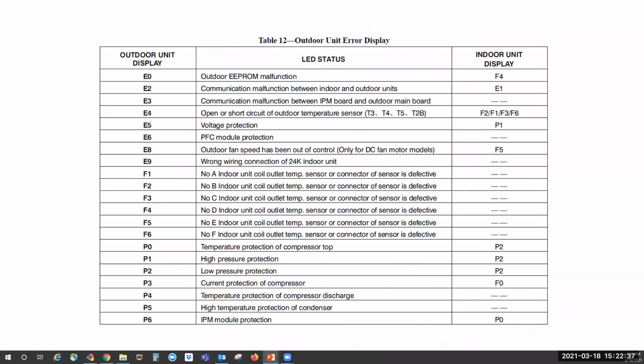If you have an error code indoors, you want to go outdoors and make sure that error code matches. You'll refer to your service manual for this. Some of these outdoor units have a display. Some of them have blinky lights, so you'll have to decode what the blinking lights are. Some of them also have several colors of blinking lights.